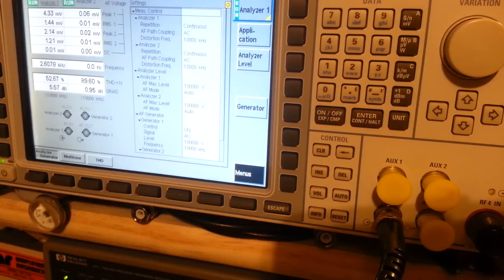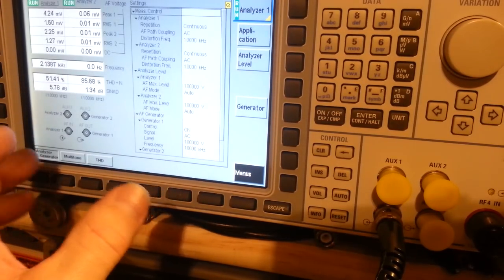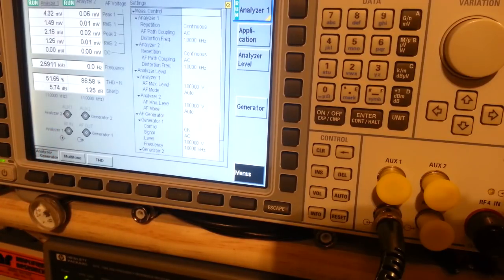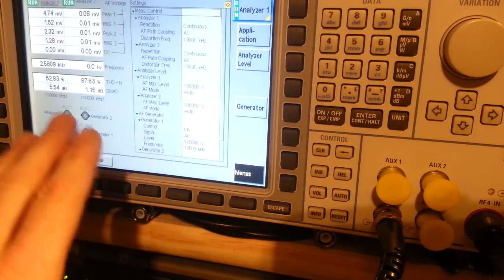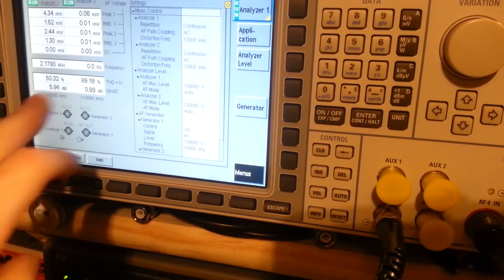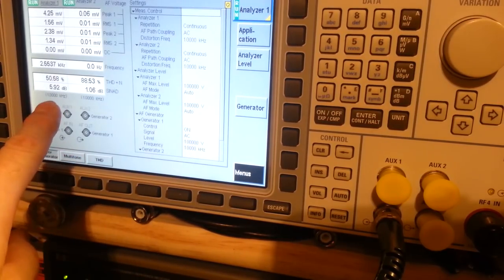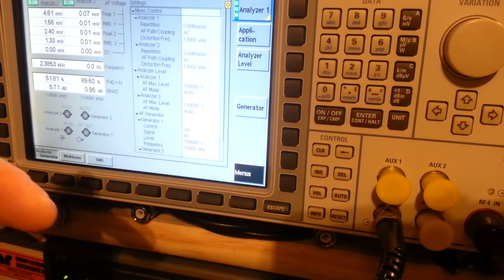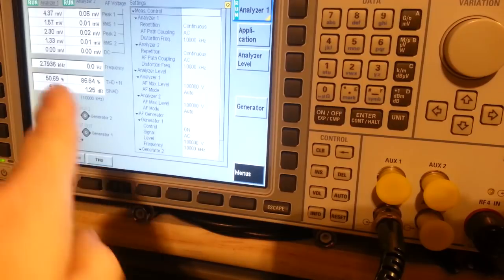I'm trying to think how to describe this without getting too technical. Like I say, it's almost impossible for an instrument to measure distortion on complex waveforms like human speech, because the frequency is continuously varying, from the lowest frequency, way down there, up to really high frequencies. It's hard for it to measure something continuously changing because it doesn't know what to measure at any given time. That's why we use a solid 1000 hertz audio tone. It uses that as the reference level. It knows 1000 hertz is the modulation into the radio, and it wants to see what comes out.